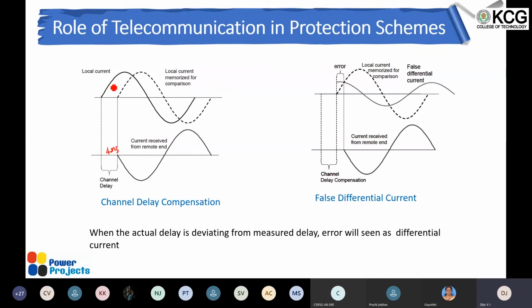there is always a resultant current, right? So what the relay will do is, based on the communication delay, it will shift the local end current, because it can process the local end current easily, since it gets that value directly. It gives a shift of this 4 millisecond before the calculation of the resultant current. This is what is called local current memorized for comparison. The local current actually happened 4 millisecond early, but from memory it takes what the value was at 4 millisecond, and then those two values are compared. Then again the resultant is 0. So for an external fault, we are ensuring that the relay won't maloperate.